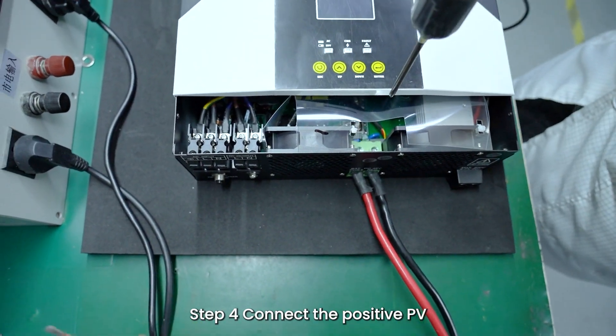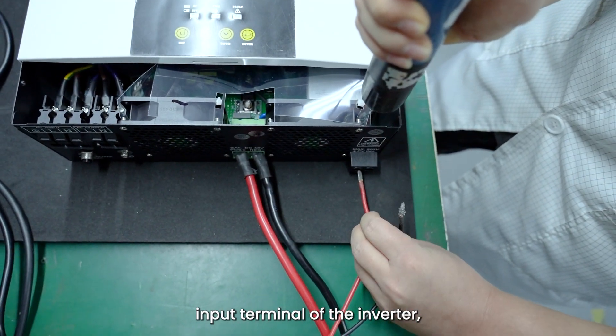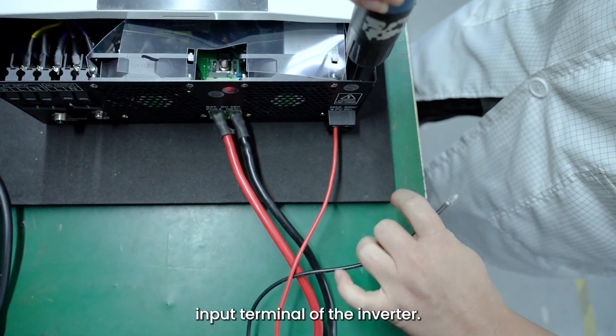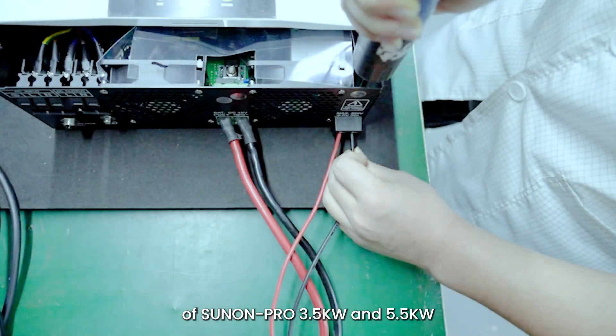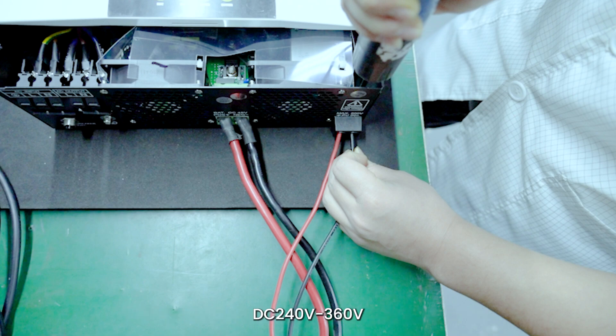Step 4: Connect the positive PV wire to the positive PV input terminal of the inverter, and then connect the negative PV wire to the negative PV input terminal of the inverter. Note: The PV input open circuit voltage of Sunon Pro 3.5 kW and 5.5 kW inverter shall not exceed 500V. The optimal operating voltage of the module is DC 240V–360V. The maximum PV input power of Sunon Pro 3.5 kW is 5000W.